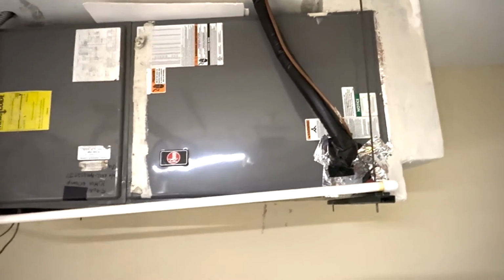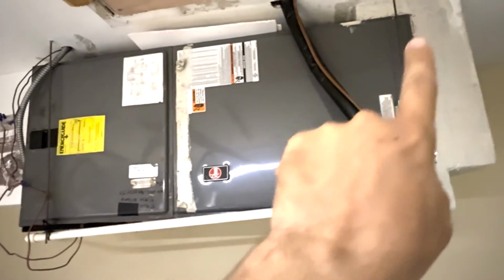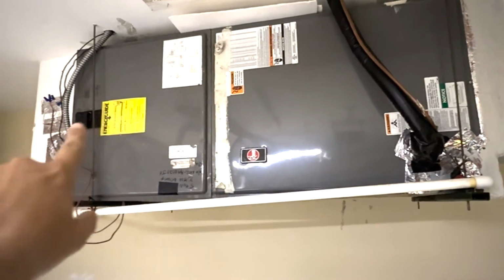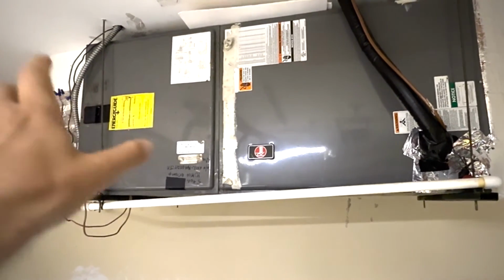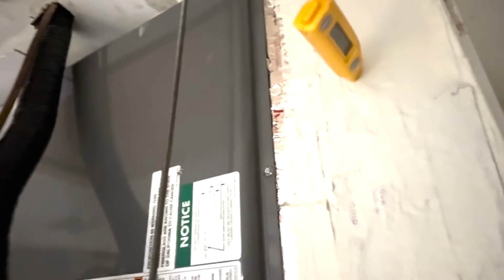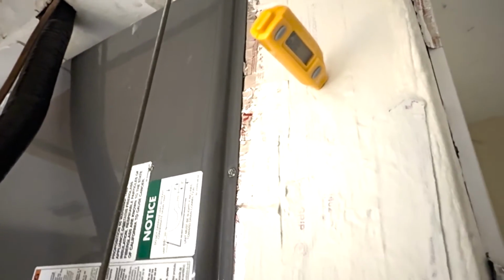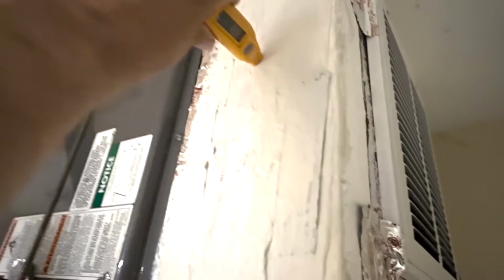That's going to give you the temperature of the air coming up your filter. And then it goes across your coil, and then it's going out to your supply side, which is going to supply all of your grills. So if you take a temperature probe, something like this, and you stick it in one side of your plenum, it's going to give you the temperature on the return side, which is the temperature inside your house.